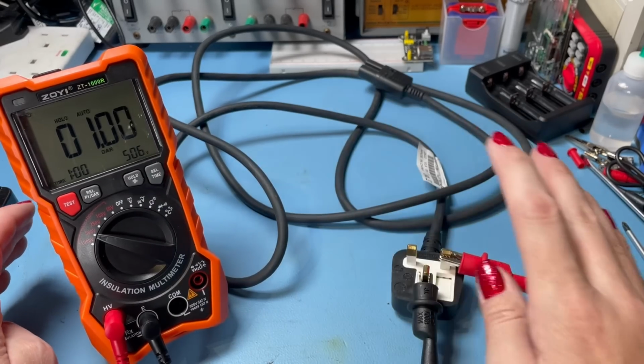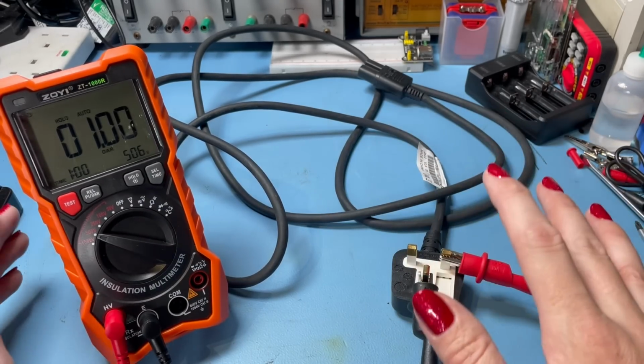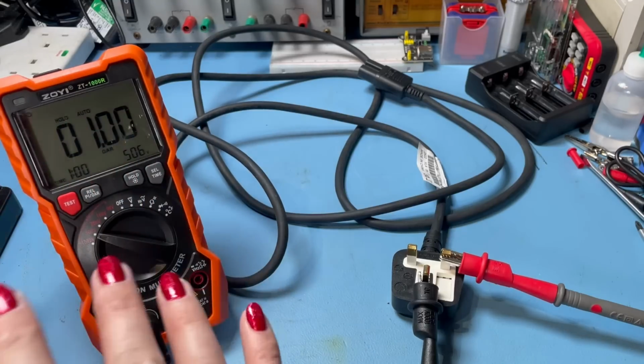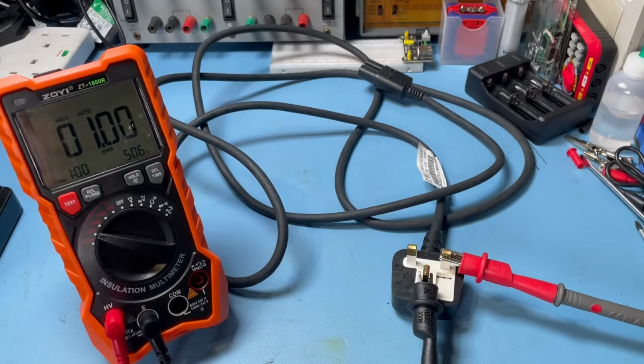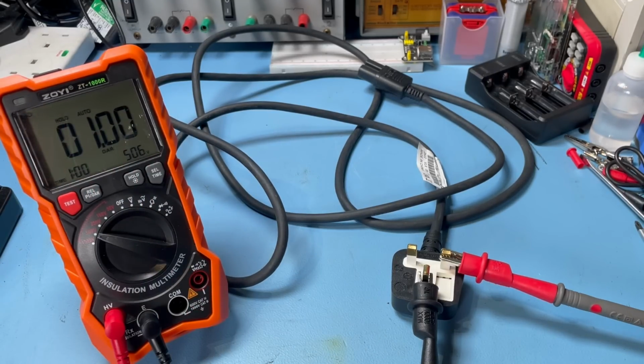So if you do a DAR test on something, a cable or an appliance, and the reading you get is a bit spurious, you're not sure, then I would do a PI reading on it. You've got to have a bit more patience, it takes 10 minutes.